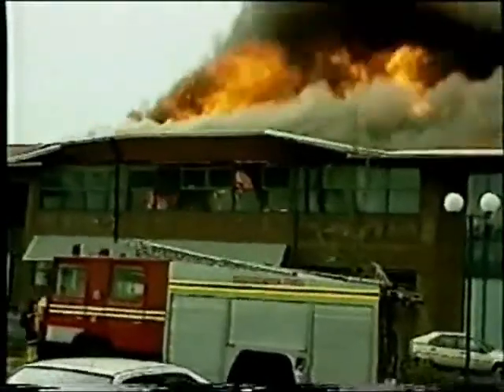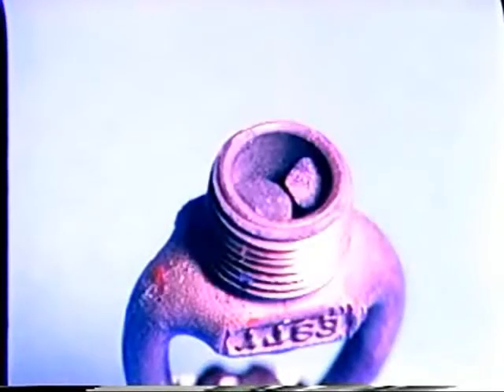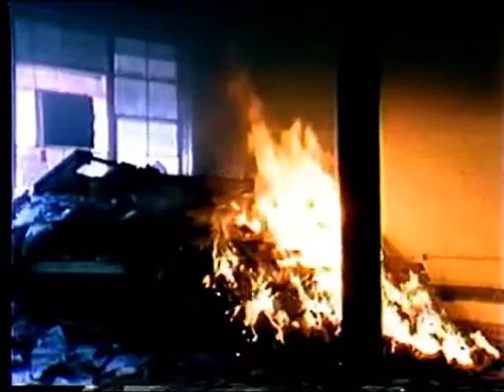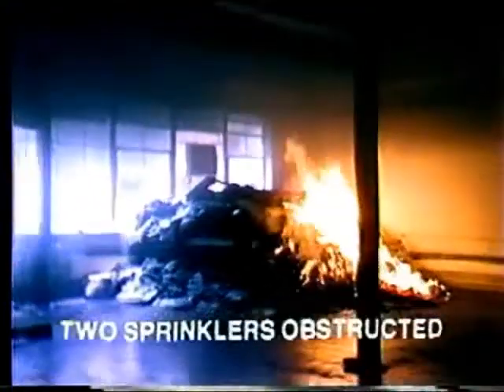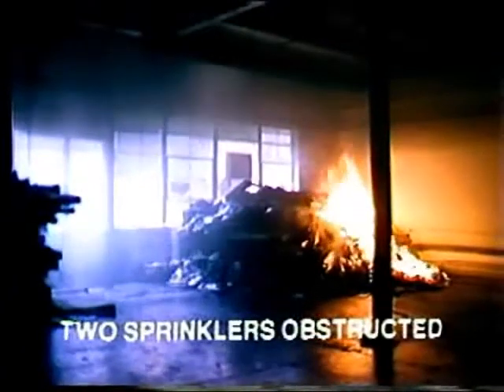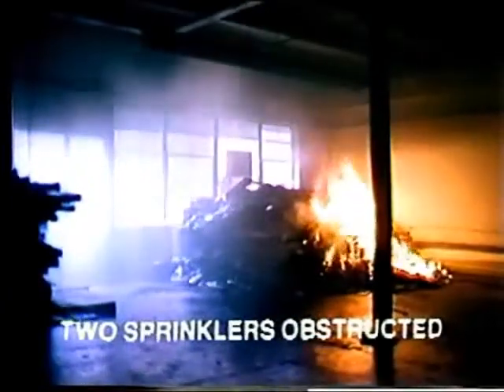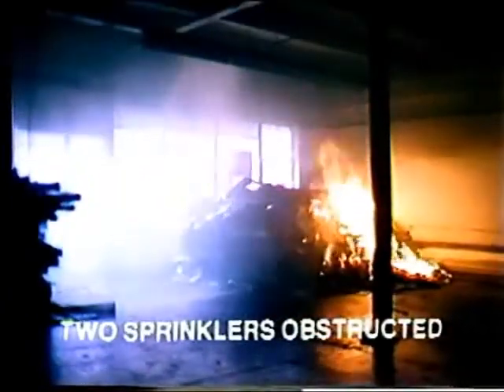Impairments are also caused by obstructions within the sprinkler piping system, such as rocks or other debris, preventing water flow to the fire location. When water can't discharge from heads over the fire, it grows, and its intense heat opens nearby heads, including those over areas unaffected by the obstruction. When a large number of heads operate, the water supply is very likely to be rapidly overtaxed.